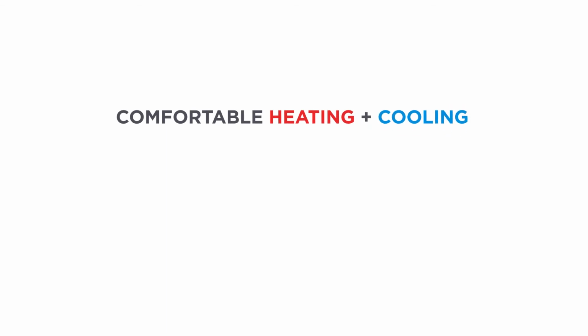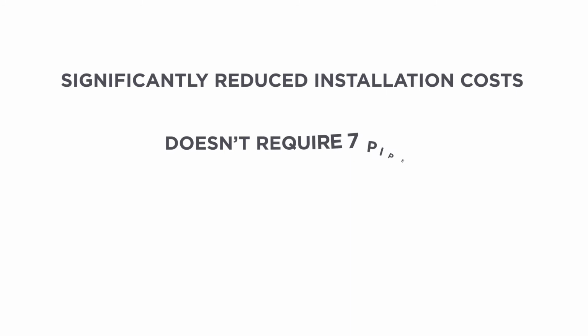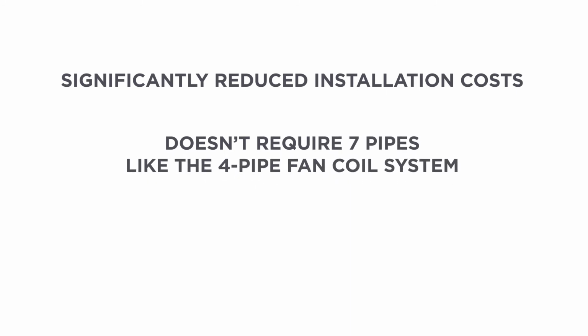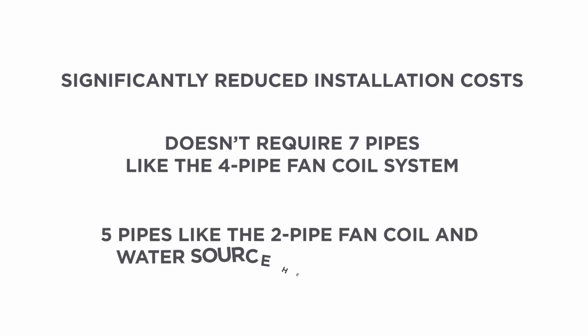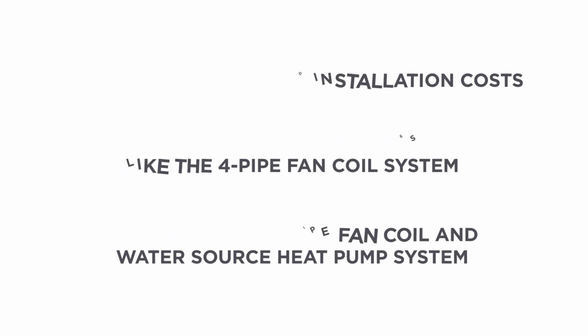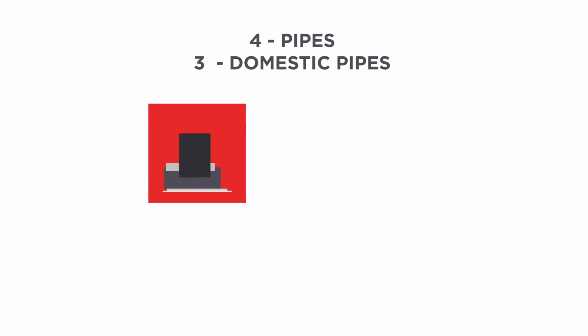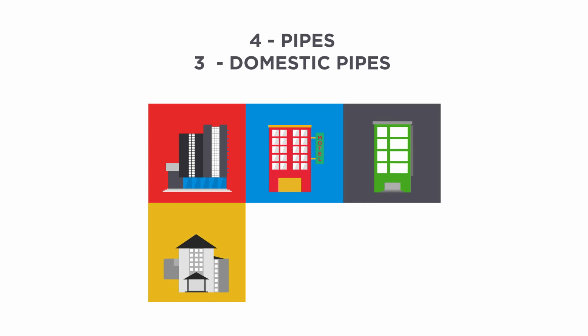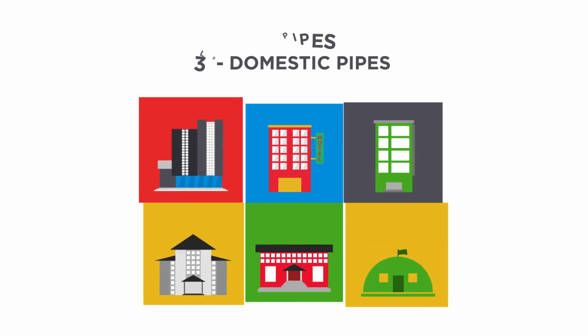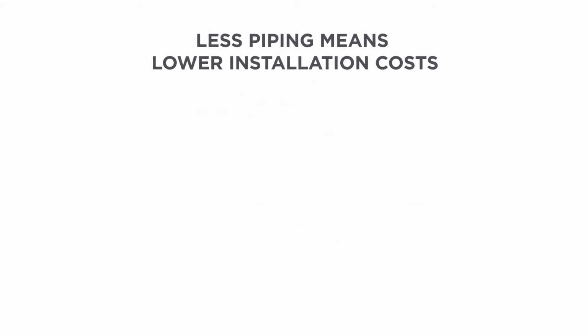1. It offers comfortable heating and cooling as selected by the tenant or guest in the space itself from the thermostat. 2. It offers significantly reduced installation costs, as it doesn't require 7 pipes like the 4-pipe fan coil or 5 pipes like the 2-pipe fan coil and water source heat pump system. IPS instead uses 4 pipes, 3 of which are domestic and already required in our target buildings: hotels, motels, condo, senior housing, dorm, and army barracks. Less piping means lower installation costs.